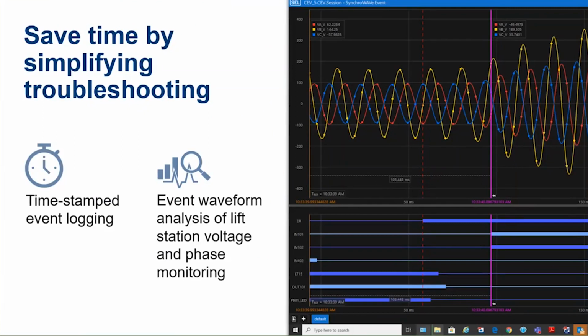That is a time frame of 103 milliseconds, right? A tenth of a second. And so what you can see is the voltage has sagged significantly, because we should be seeing 230 volts on the yellow trace, and the blue and the red should be about 120. And the voltage sagged so significantly that it dropped out some of the inputs, which caused the pump controller to shut off the pumps. This way, the customer knew that they have a generator problem, and that when they start up a pump, it was dragging that generator down, and they need to take a look at it, as opposed to just getting a phase monitor indication and not really knowing what happened.